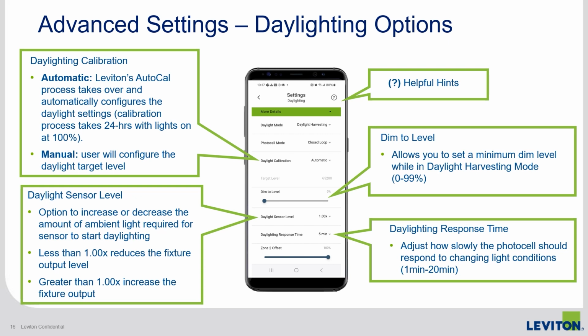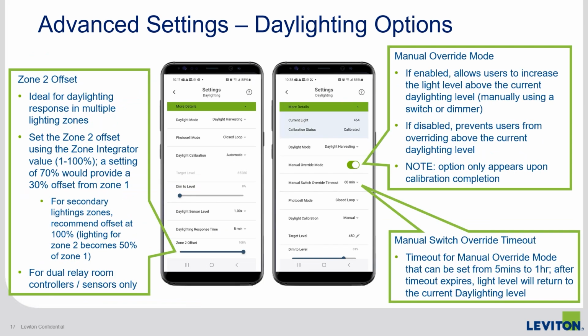For daylight harvesting applications, you can select a minimum dim to level. The lighting will never dim below this value even if the space is flooded with an extraordinary amount of natural ambient light. Next is the daylight sensor level. Once a target level has been set, you have another option to increase or decrease the amount of ambient light required to begin daylighting. For the daylighting response time, this is the amount of time the sensor will respond to changes in lighting, making the transition nearly invisible to the human eye. If there is a switch or dimmer connected to the sensor and the energy codes allow for it, you can enable the manual override mode.